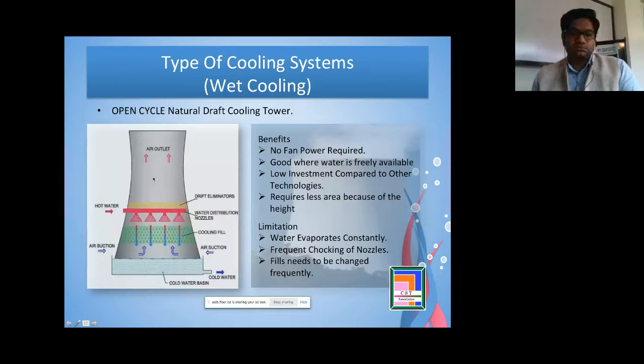But on the other end, there is constant evaporation, at the rate of 2.9 cubic meters of water every hour per megawatt. So we can have a quick look at the benefits and limitations. The benefit is there is no power consumption, and it is good where water is freely available.